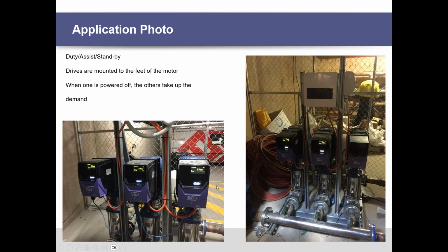So as you can see, with the way we mounted these IP66 units, we just mounted them directly onto the motors, and that means that the cabinet here only has the 3 circuit breakers, one for each of the drives. Everything else is self-contained in the drives.